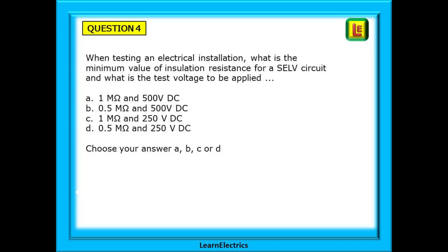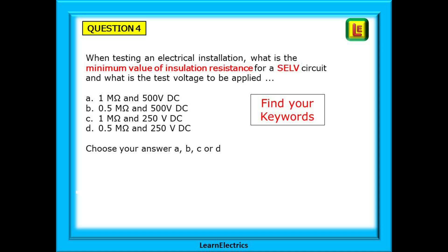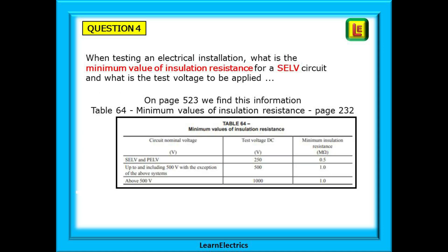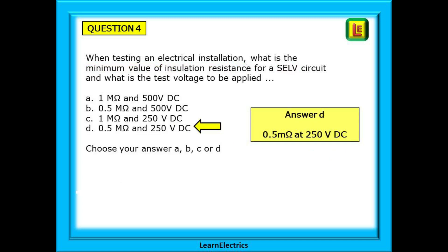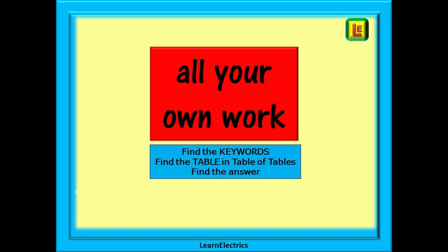On to question 4. When testing an electrical installation, what is the minimum value of insulation resistance for a SELV circuit and what is the test voltage to be applied? Choose your answer from the four offered. Find the keywords. On page 523, we find Table 64, 'Minimum values of insulation resistance', and it tells us to go to page 232. Here is the table — almost every exam will ask you a question on this table. Use the keyword to find the SELV row and there is your answer. We should choose answer D: 0.5 megaohms and 250 volts DC.